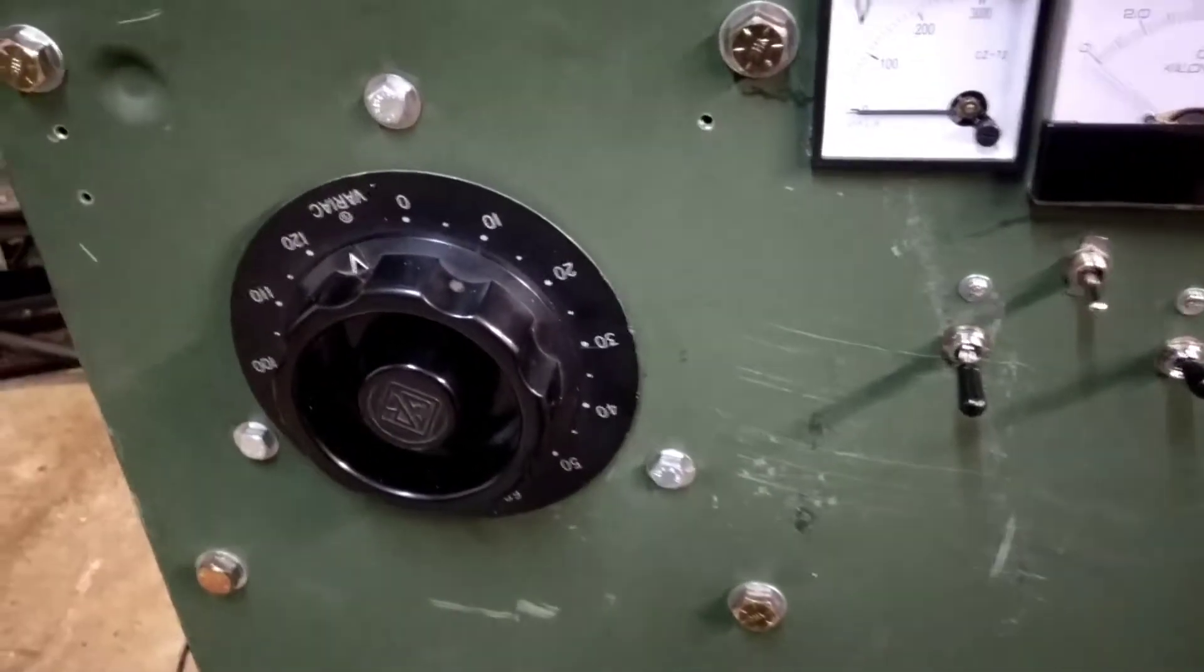What this is comprised of is a power pole transformer that's been removed from the case down there in the base of it. There is a breaker right down there in the bottom. Then there's the first contactor, the second contactor. The green thing is a resistor jumper to cross there to allow for a soft start.